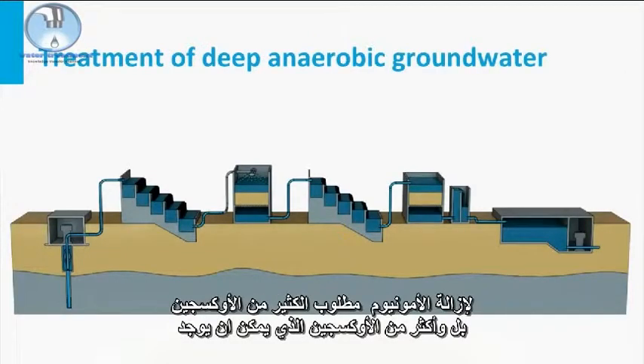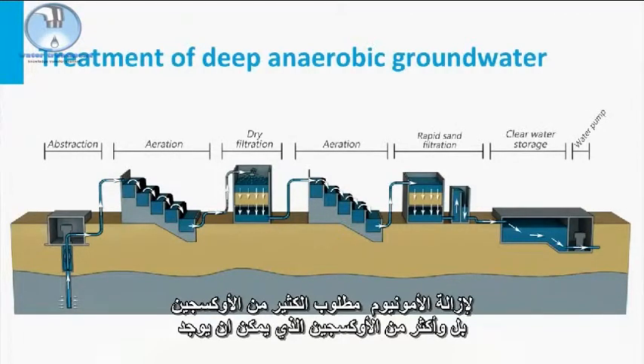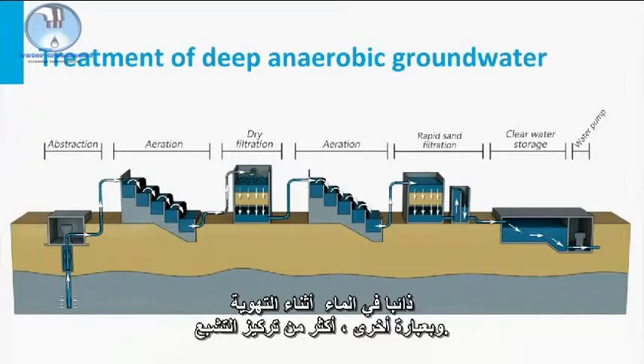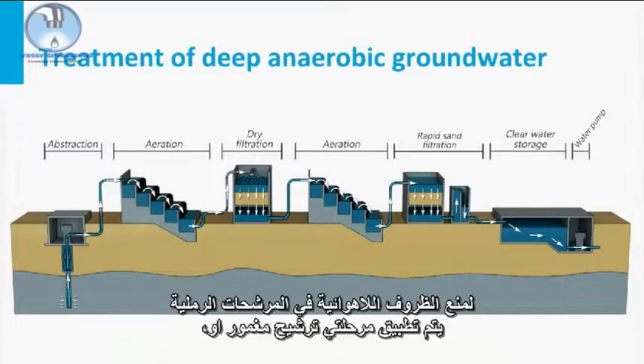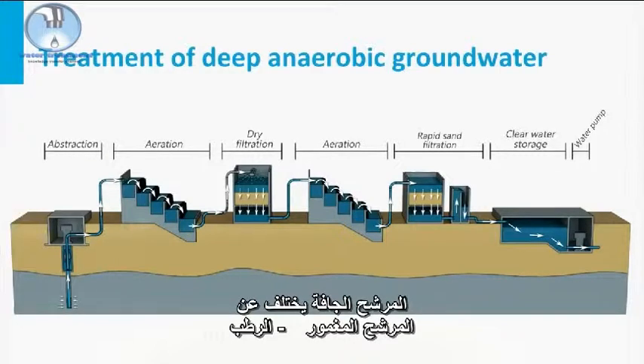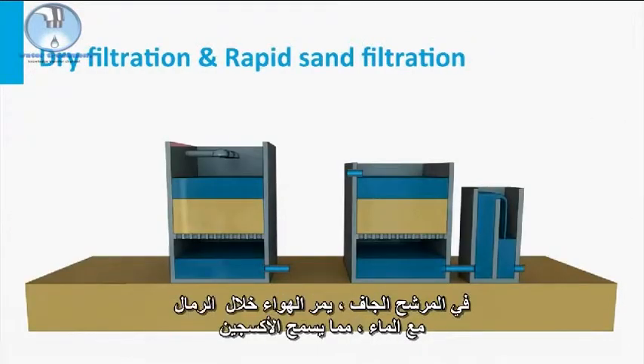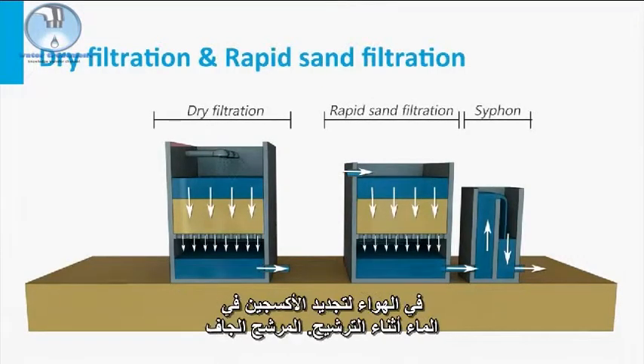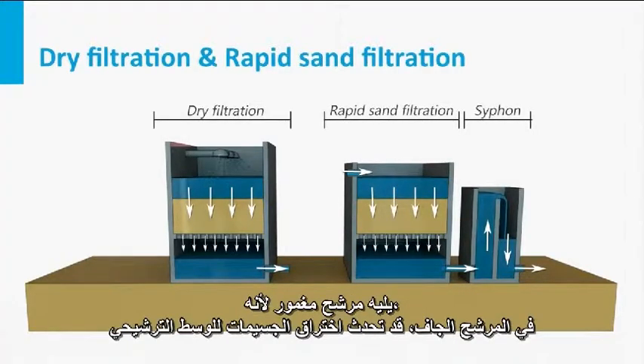For the removal of ammonium, a lot of oxygen is required — even more than can be dissolved in the water during aeration, in other words, more than the saturation concentration. To prevent anaerobic conditions in the sand filter, double submerged filtration or dry filtration can be applied, followed by regular submerged filtration in cases of high ammonium concentrations. In a dry filter, air passes along the sand grains together with the water, allowing oxygen in the air to replenish the oxygen in the water during filtration. Dry filtration is followed by submerged filtration because in a dry filter, breakthrough of particles may occur.